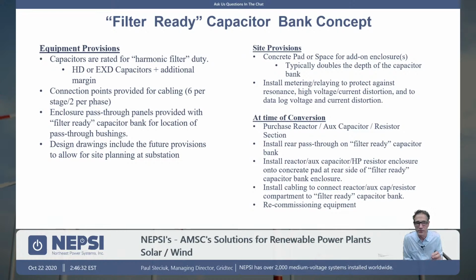We oftentimes get phone calls that say, hey, I've got a resonance issue, I just purchased this cap bank, can I convert it to a harmonic filter? We ask a few questions and we find out that they didn't have space in the substation for the reactors or the resistors. The capacitors don't have the voltage rating they need, and the customer, the renewables developer, is out of luck. They're out of luck because they purchased something and they can't use it.